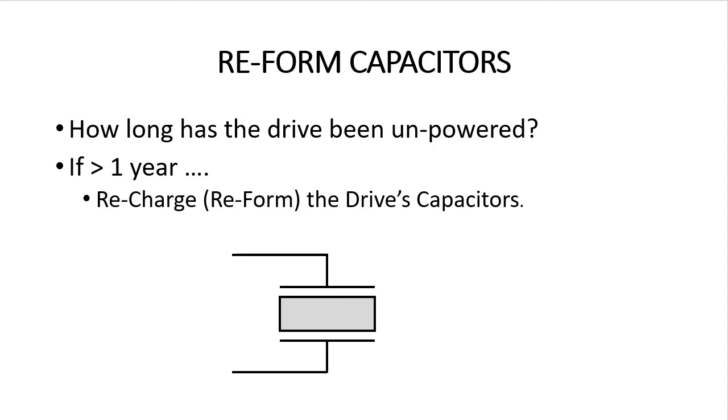Why? Because the big capacitors in the drive discharge over time, which relaxes the oxide in the insulation layer of the capacitor. If you apply a voltage when the capacitors are discharged, then the capacitors are essentially a short circuit...